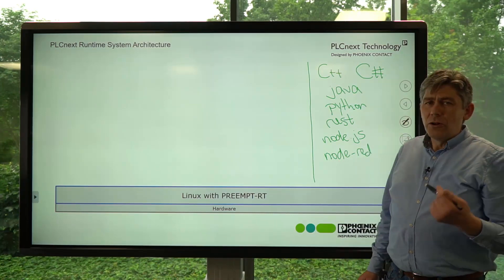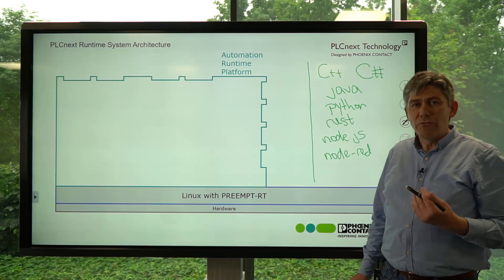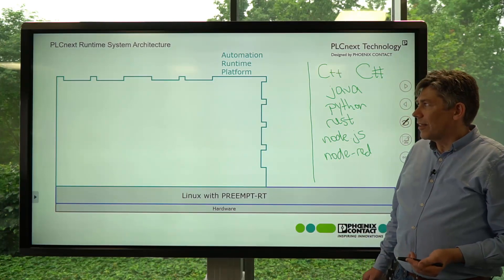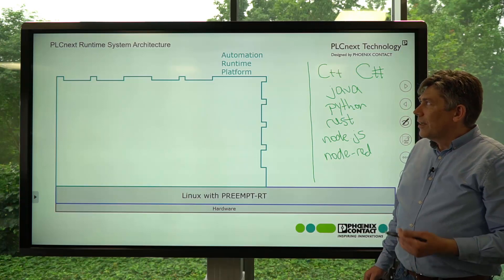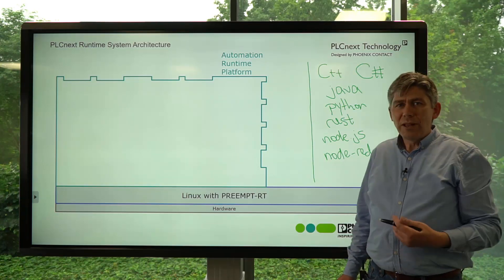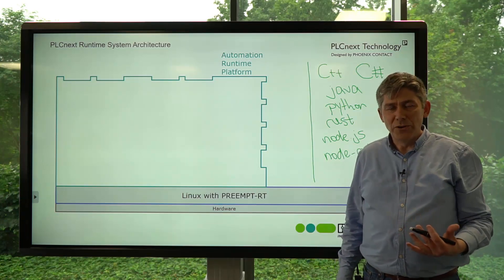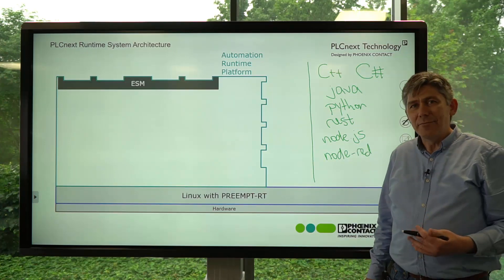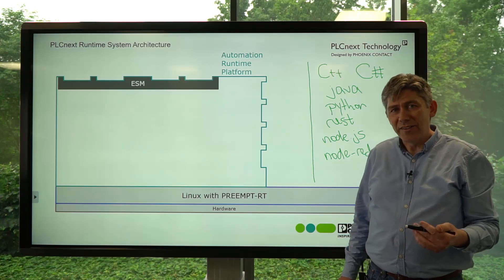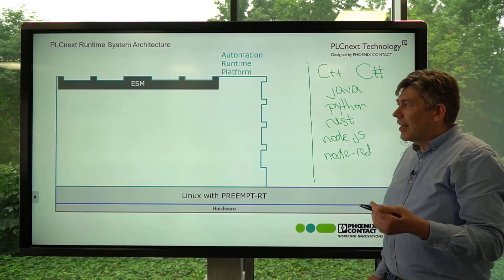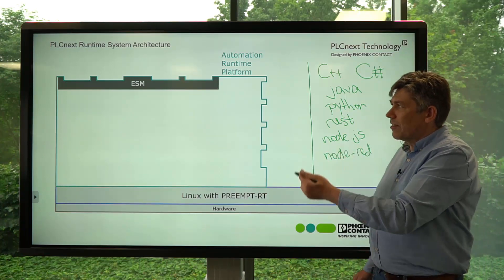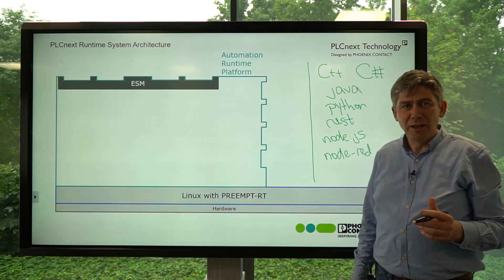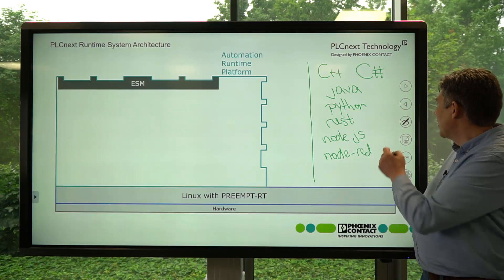But each PLCnext control also comes with an Automation Runtime Platform, and this is started up when the operating system starts. Inside the Automation Runtime Platform is a whole set of components. The first component I'll speak to you about is the ESM — the Execution and Synchronization Manager. This allows us to run deterministic real-time programs without having to worry about all the operating system level details of how to do that.